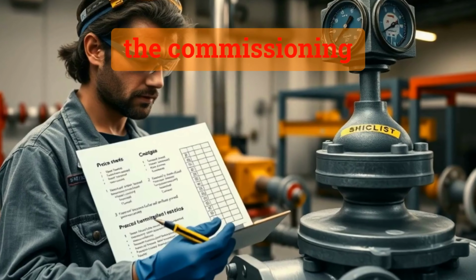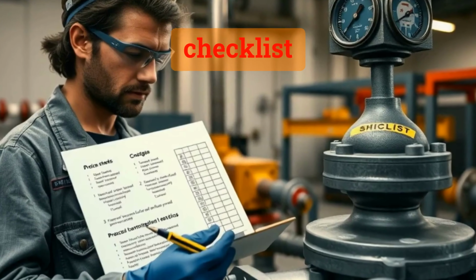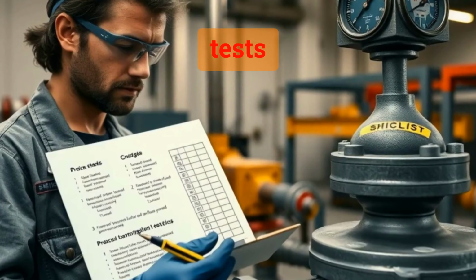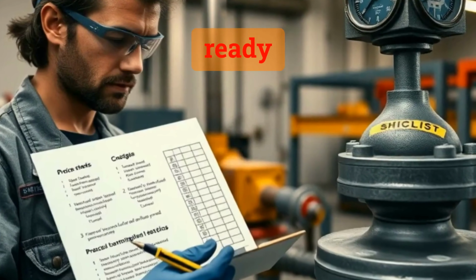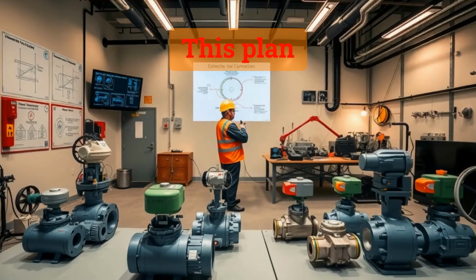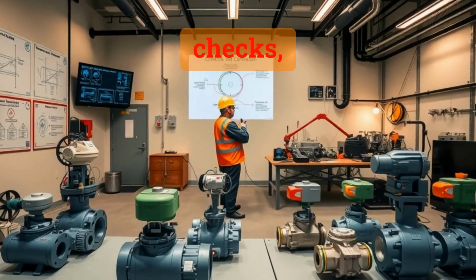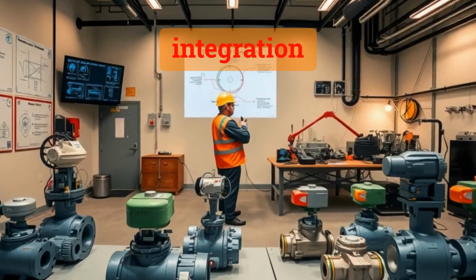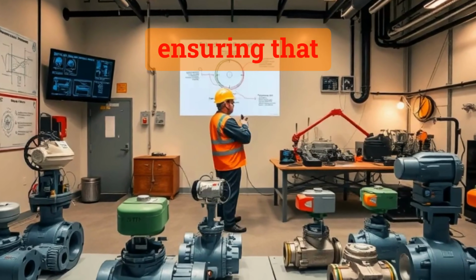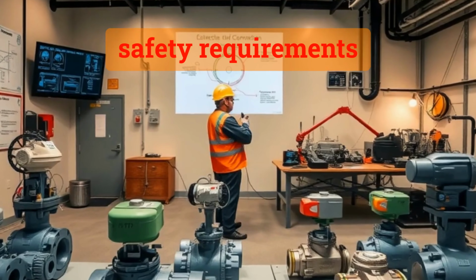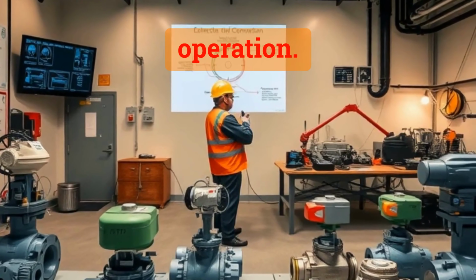Finally, the commissioning test plan is a comprehensive checklist of inspections and functional tests performed before a valve is declared ready for service. This plan typically includes stroke checks, pressure testing, and integration with control systems, ensuring that every valve meets performance and safety requirements before entering operation.